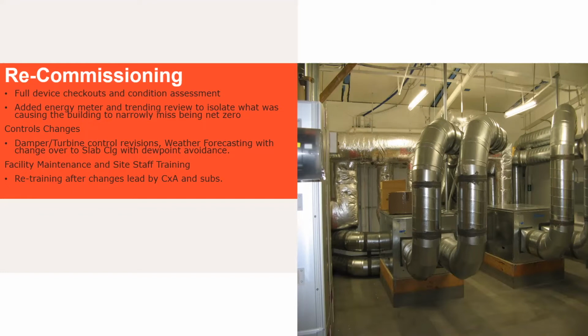What approach did you use on dew point avoidance? We stuck to 2 degrees, but we had slab temps in every single room, and we used the lowest 2 values as our reference points to avoid condensation, giving ourselves a big buffer. People wanted 5 degrees, but that was too far off to get good enough cooling from your slab. It was adjustable though.